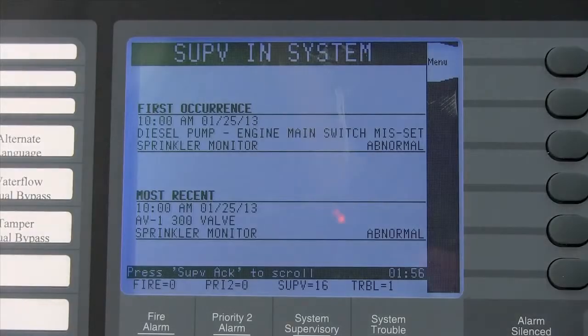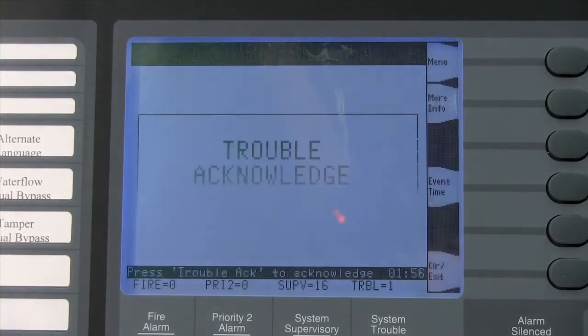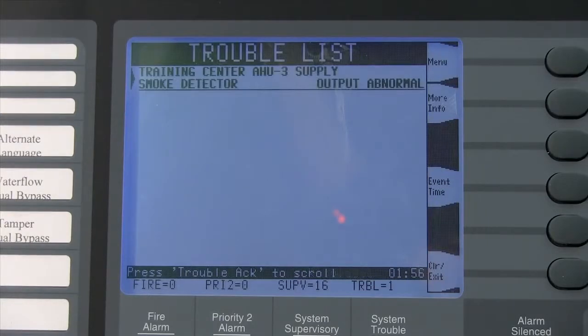Here you can see that the panel is indicating a duct detector abnormal trouble. Let me silence it. At the duct detector unit, I would see that my airflow has been reduced, indicating a possible rupture or obstruction of the sampling tubes, or perhaps a dirty filter. A trouble could also signal that the airflow has increased past calibration limits due to open or ruptured return or exhaust piping.